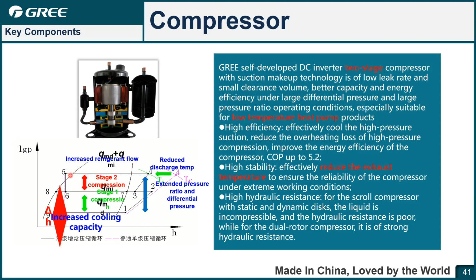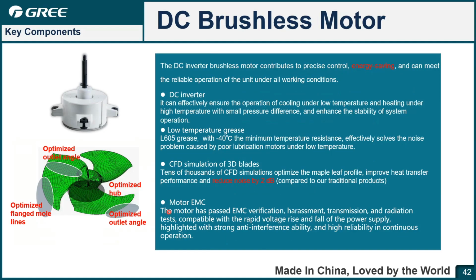And also for the VERSATI 3 is double stage throttling. Yeah, so actually in cooling mode, the economizer can improve the cooling capacity. You can get additional capacity improvement. So in general, by this compressor, first you can get a very wide operation range. The second benefit is the cooling capacity is improved. For the fan motor is the DC brushless motor. So for this motor, you know that the efficiency is high comparing with the ordinary AC motor. Also, the running noise is lower.